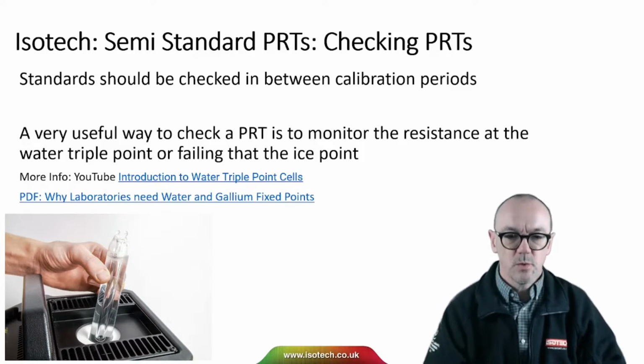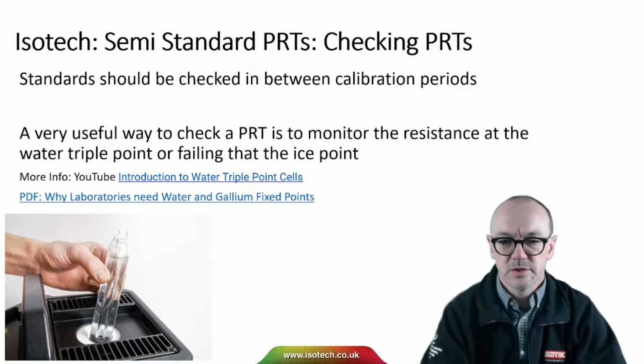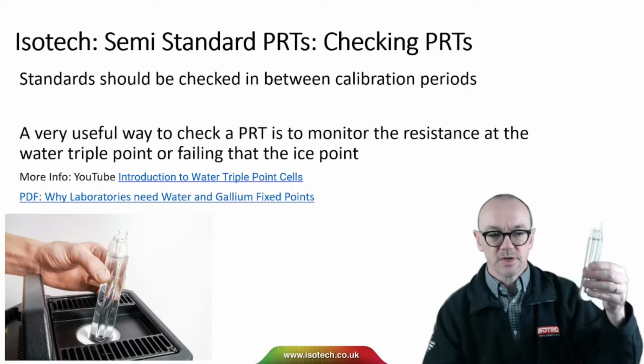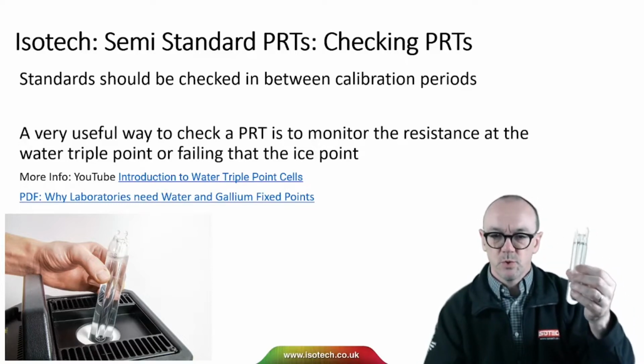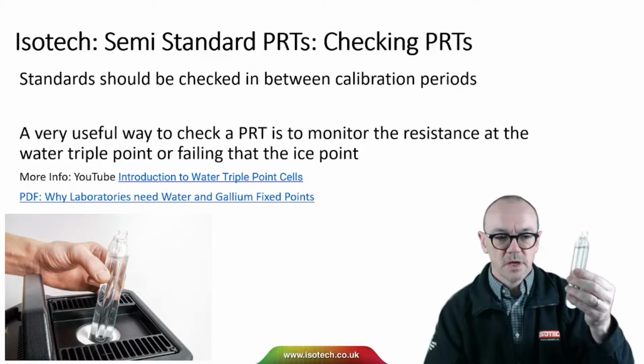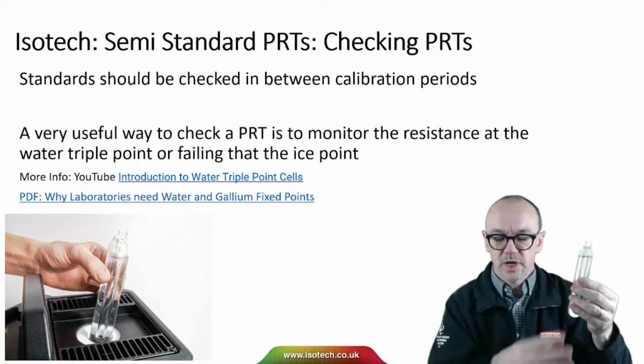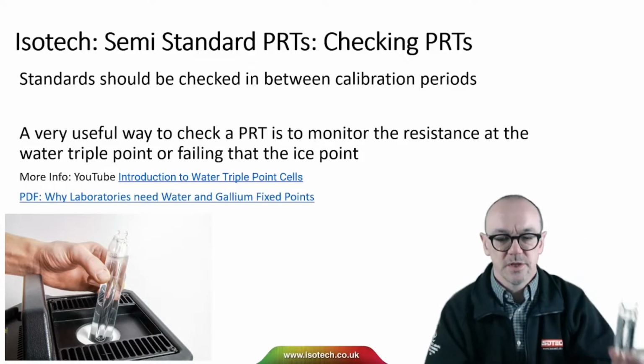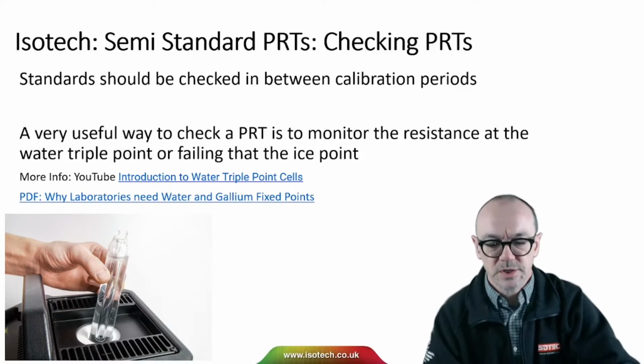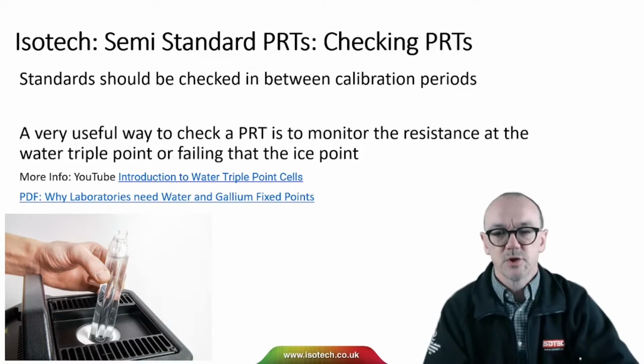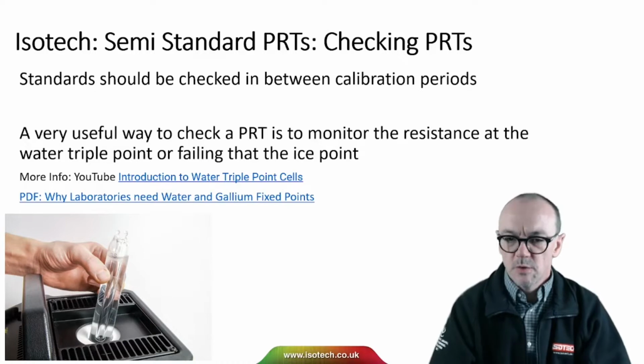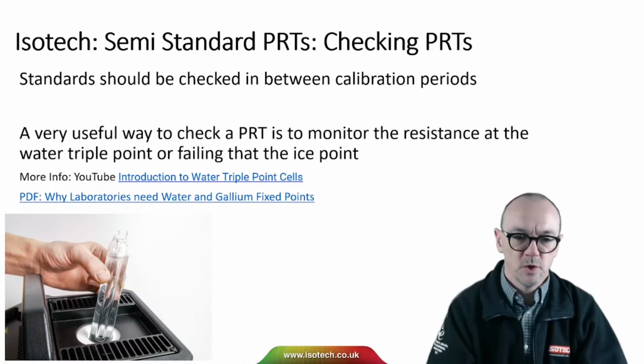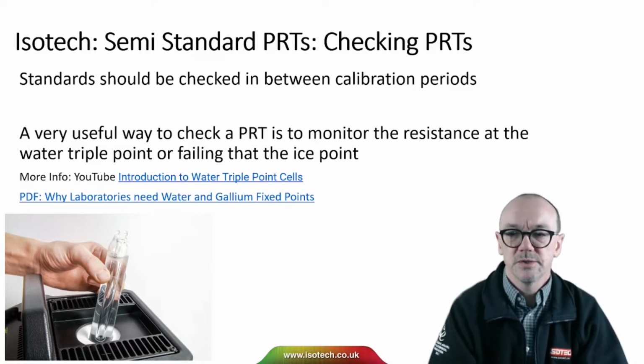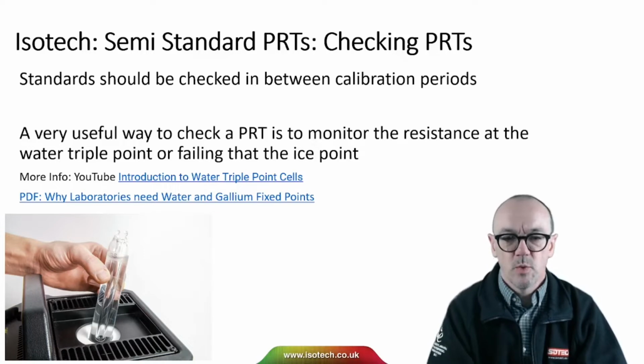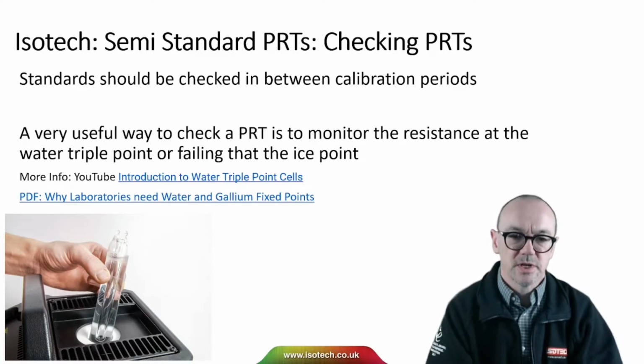And a very useful way of doing that is to check the resistance maybe in a water triple point cell. These can be relatively small, relatively low cost, and with a water triple point cell we can check a PRT with an uncertainty of perhaps a few thousandths of degrees C quite easily. Cells come in different sizes and types. For more information, we've got a YouTube guide to water triple point cells. We've also got an article on our website about why laboratories need water and gallium fixed point cells.